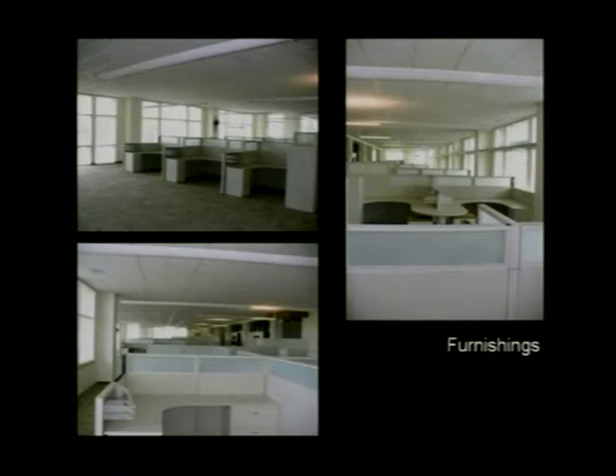Ken? Steve, you remember what the electric lighting power density was? I don't. Jeff, do you know? Yeah, in the open office areas, it came out to about 0.71. So, can you repeat that so everybody can hear? You asked what the electric light power density was? Power densities in the open office areas came out to approximately 0.7 watts. It was about just under half of what code allowed.